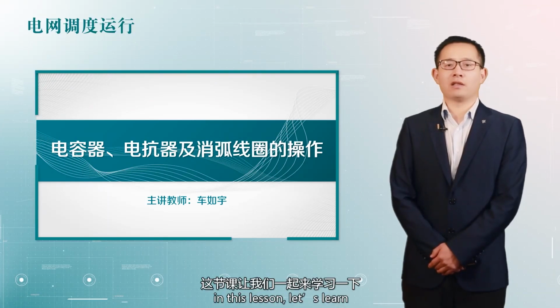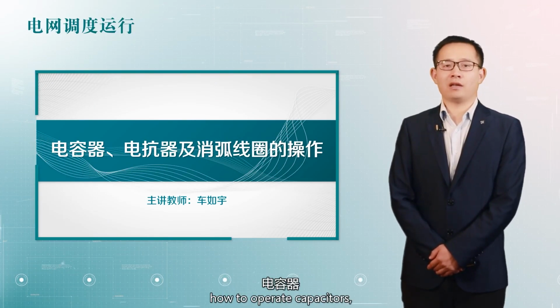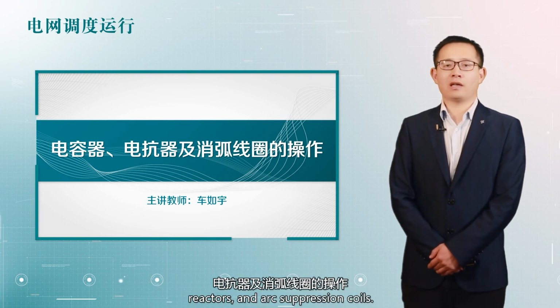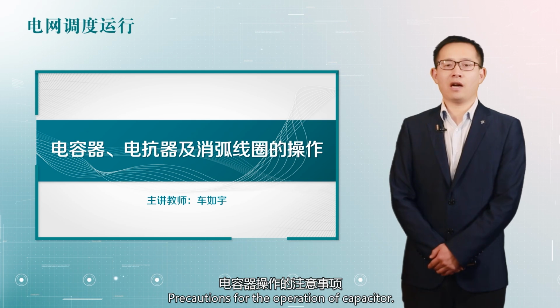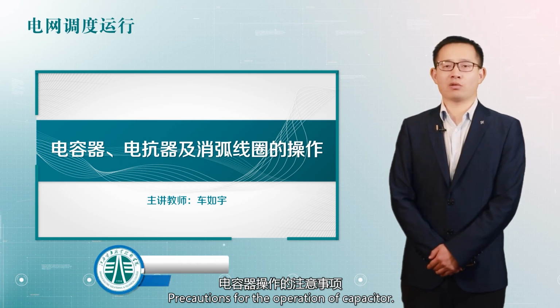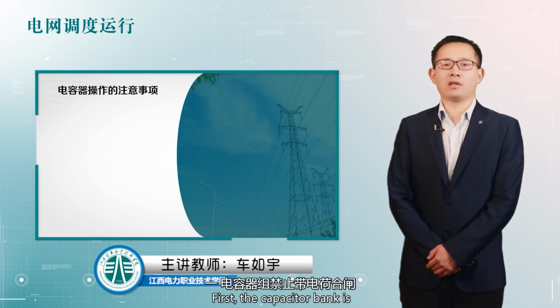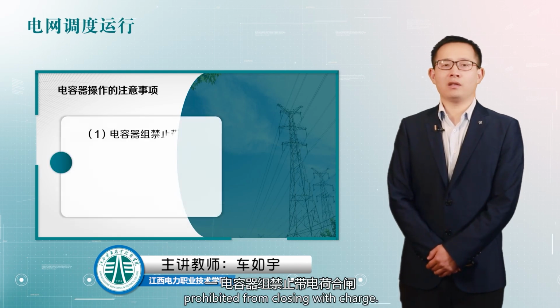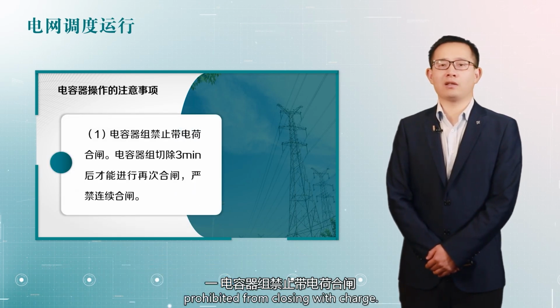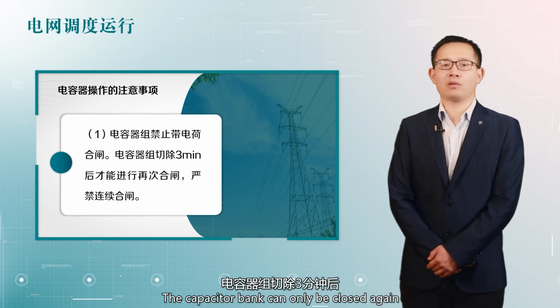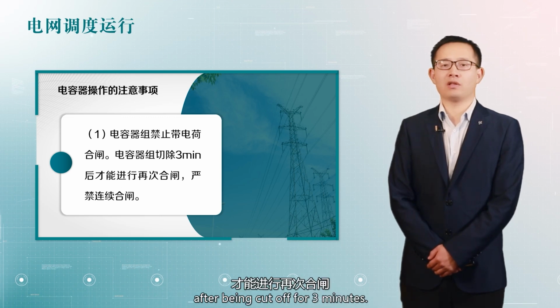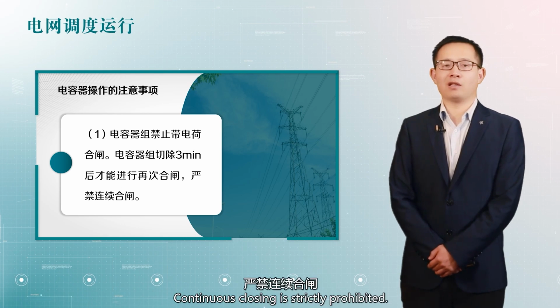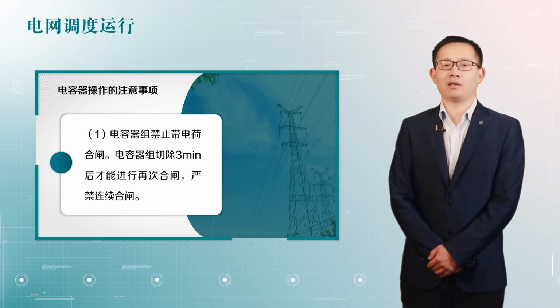Hello everyone, in this lesson, let's learn how to operate capacitors, reactors, and arc suppression coils. Precautions for the operation of capacitors. First, the capacitor bank is prohibited from closing with charge. The capacitor bank can only be closed again after being cut off for 3 minutes. Continuous closing is strictly prohibited.